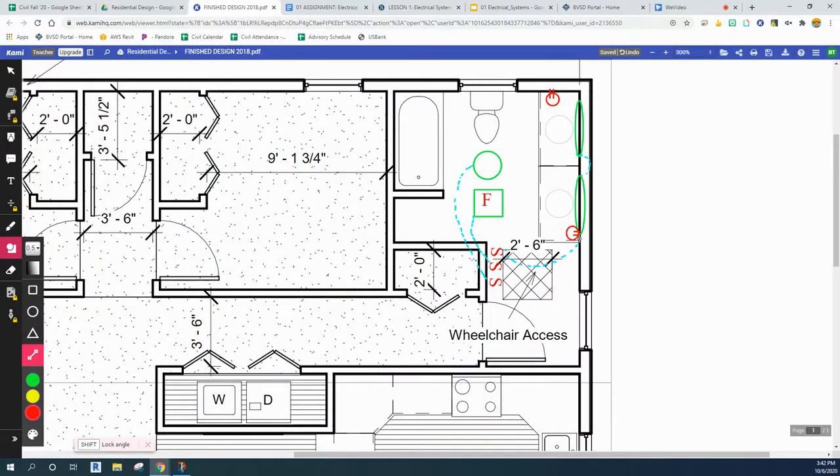The last thing I need to do is I need to declare that this is a GFCI. GFCI, again, is what you would have if you have a receptacle anywhere near water. You need to have it as a GFCI. And what we could do as an electrician is we could make this the GFCI, and then we could connect this receptacle to this one, so that if any water gets in any of these receptacles, while it travels all the way back to the main panel, it will trip this and turn it off. So you only really need one of them in a bathroom.